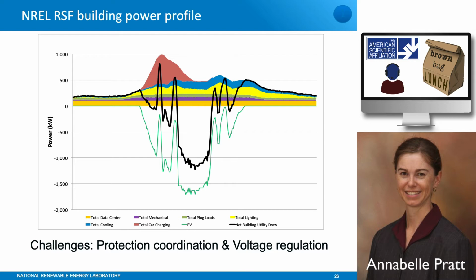The second aspect is voltage regulation. With power flow from left to right, your voltage drops as you move further down the line. But now if you have generation at the end of the line, you could actually have voltages that increase as you go down the line. So it becomes more difficult for the utility to manage your voltage. They're obligated to supply that at 120 volts plus or minus a few percentage points. So a lot of work is going into algorithms being built into distribution management systems to aid with voltage regulation as well.